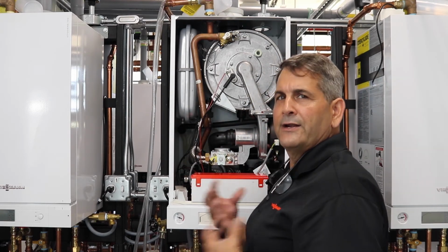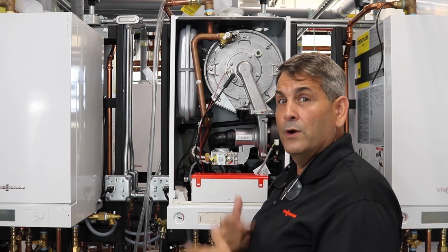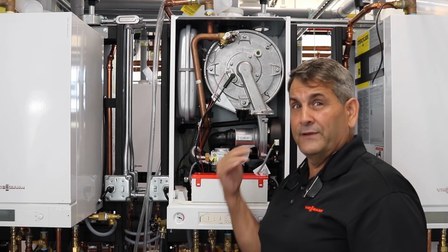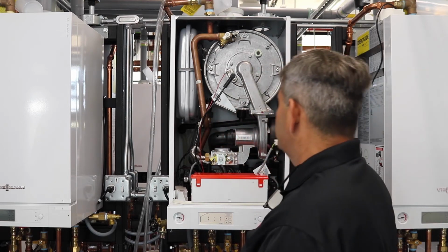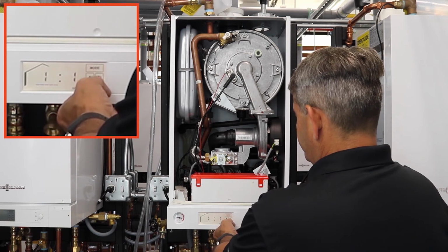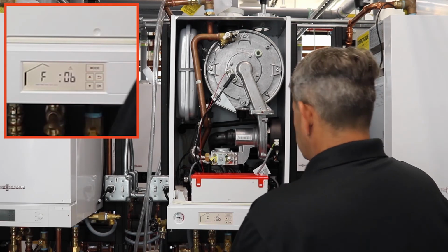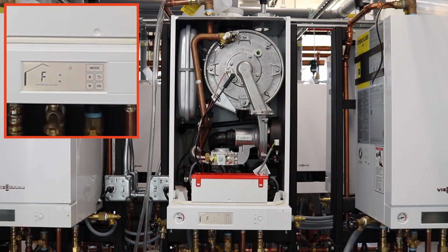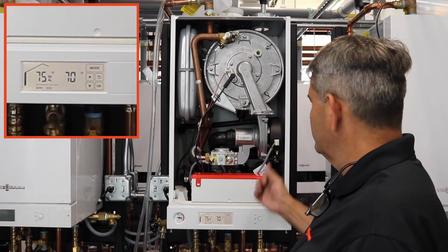In the beginning you heard all that gurgling and noise, and normally when people call tech support, they say that they can hear the water going through the boiler. We know right off that it's mostly air. So now we'll open up the other valve, let it go out into the system itself. We'll take it out of purge mode. And we're going to clear our fault. This fault should clear automatically. So once we change that pot, it should clear automatically.